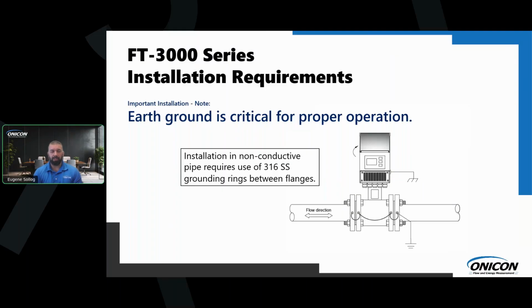The reason for this is the bolts going through are not a very good conduit for a ground because our meters have a thick epoxy coating on them, which does not always scratch off or conduct very well. So we do need those bonding points in the flange, and then taking that to an earth ground is always a great practice in conductive pipe.